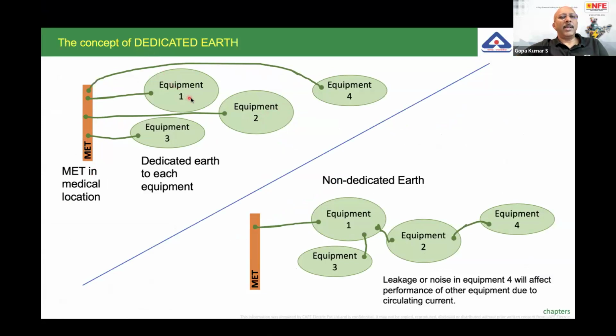Individually earthed means all these equipment 1, 2, 3, 4 are connected to the common earth bus bar individually, separately. Whereas at the bottom, what you are seeing is not individually earthed. Probably this can be called earthed in group. The problem of earthed in group is, if there is a leakage current or some noise in equipment number 4, it will flow through the other equipment to reach the MET.